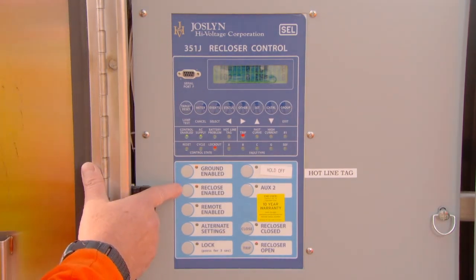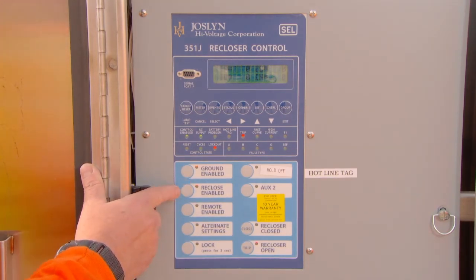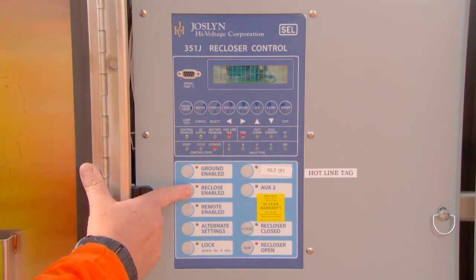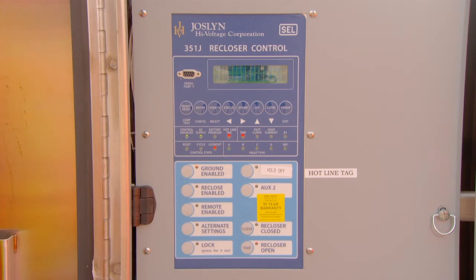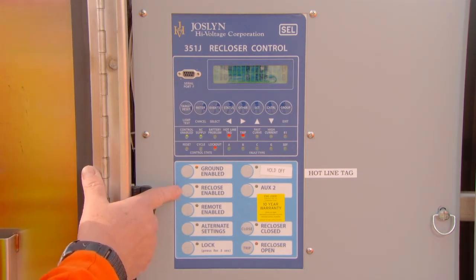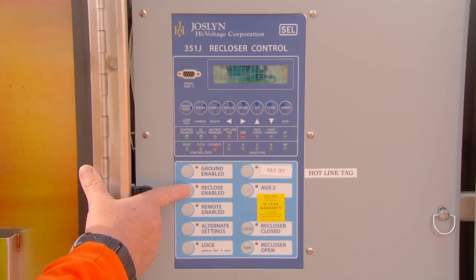The Reclose Enable button is normally on and is used if you want the control to go through the entire cycle of programmed reclose attempts. This light is amber when active. To go to only a one-shot to reclose cycle, press the button again. The amber light will now turn off.